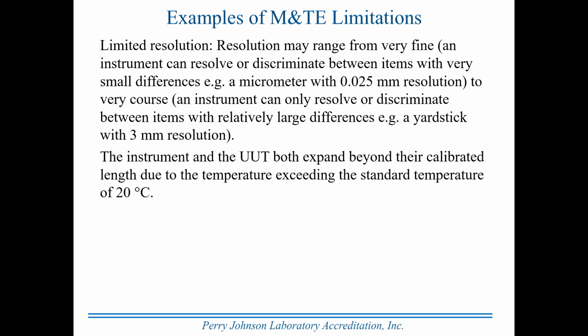The instrument and the unit under test both expand beyond their calibrated length due to temperature exceeding the standard temperature of 20 degrees C. This means laboratories engaged in either dimensional calibration or dimensional inspection must work to control their temperature and keep it, to the degree possible, at 20 degrees C, or certainly establish a small plus and minus tolerance to that.